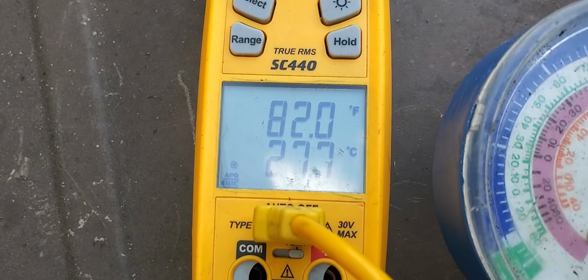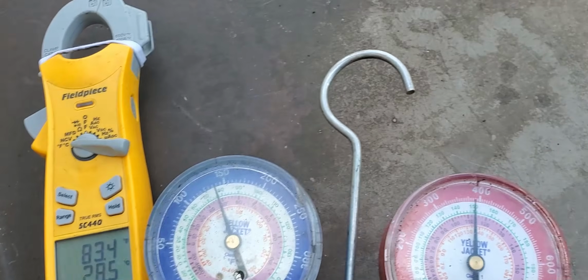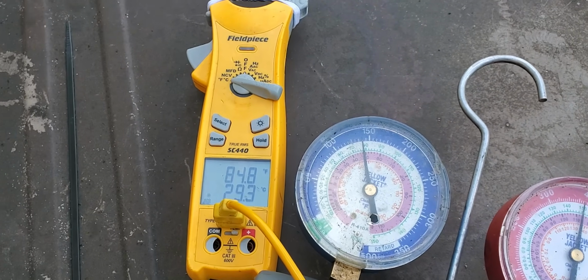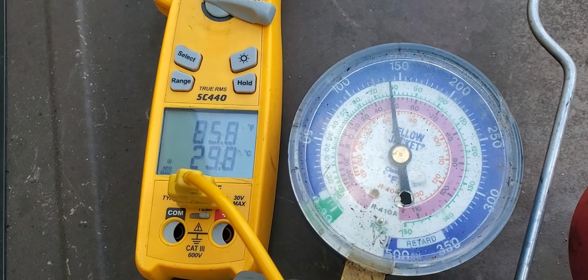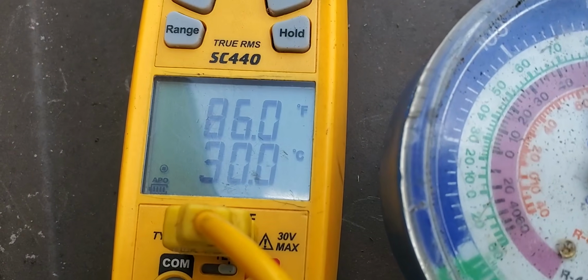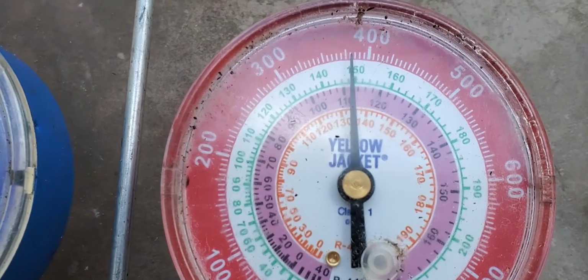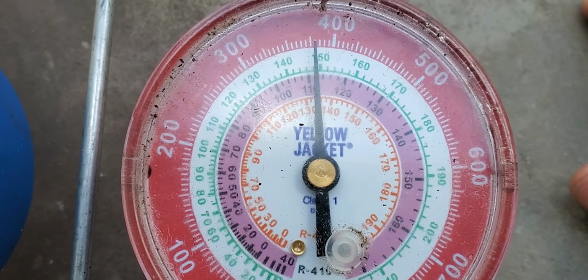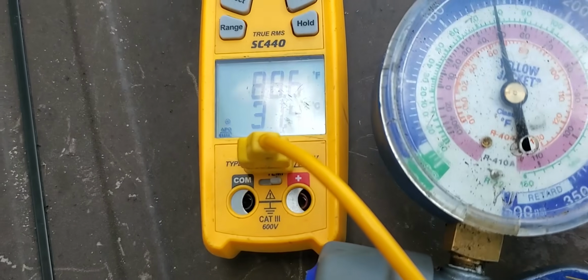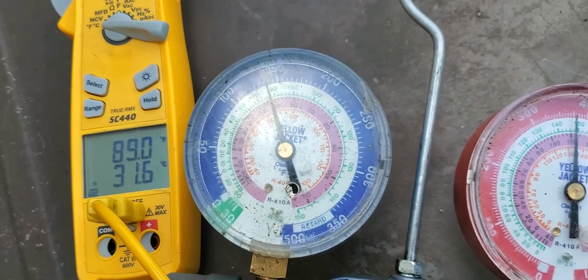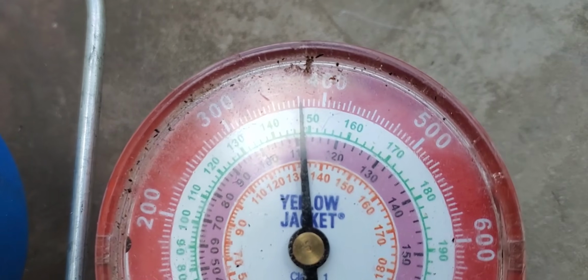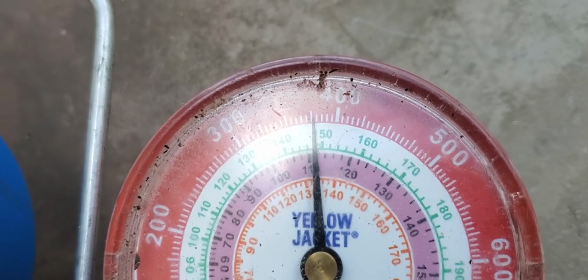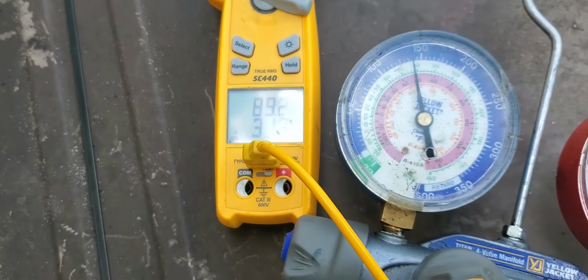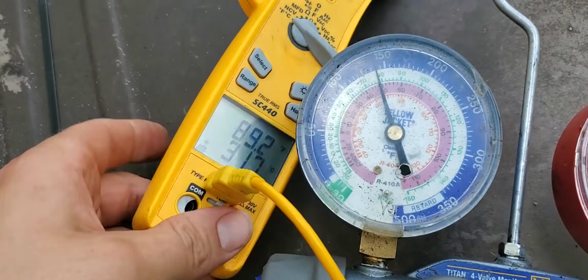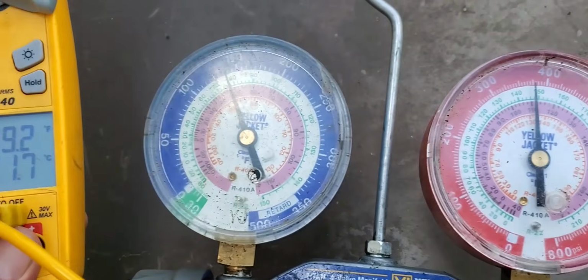I want you guys to understand exactly how I use superheat and subcooling methods and how I check using the values that I'm given. Notice the suction line temperature and the liquid line temperature now. There's a greater difference between the two measurements, and that is because both of our values, superheat and subcooling, are coming into the range which we need for us to know that both our evaporator and condenser are being flooded so that we have the total volume of refrigerant that we need for this unit to operate correctly.